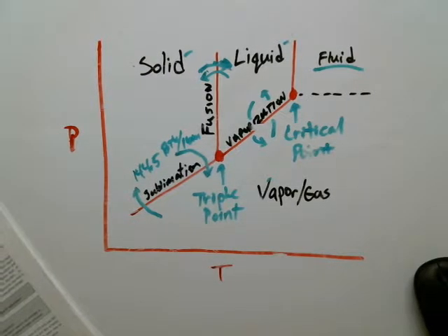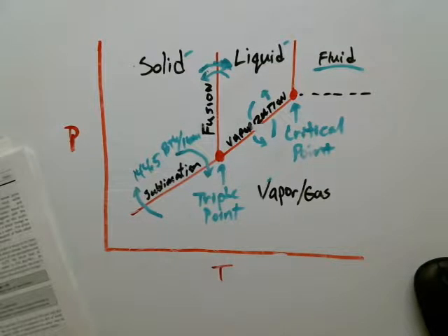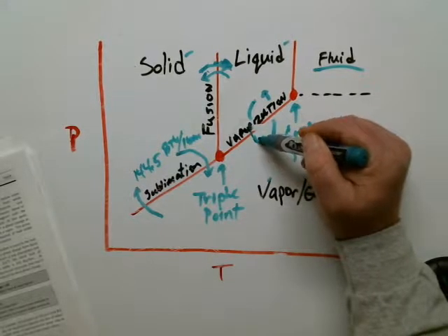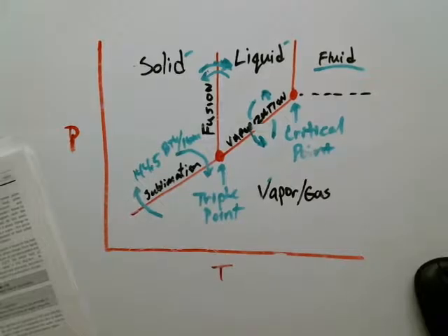Then on the right-hand side of that page, it's dealing with the latent heat of vaporization line. And we know that vaporization is where once we reach the saturated liquid point there is a latent heat addition or removal. If I was going from a liquid to a vapor, that would be a latent heat addition. If I was going from a vapor and condensing it back to a liquid, that would be a latent heat removal. It occurs at a constant temperature.